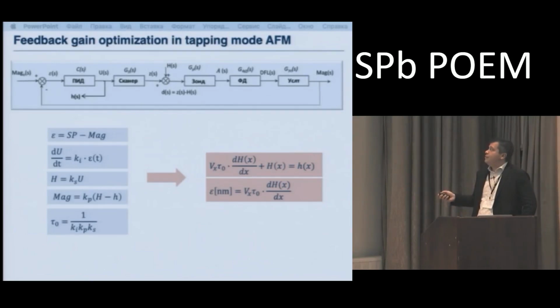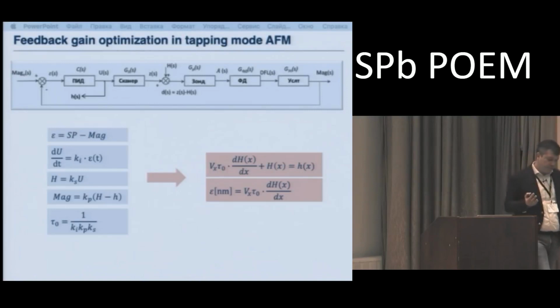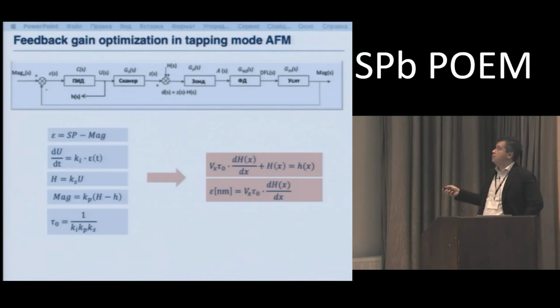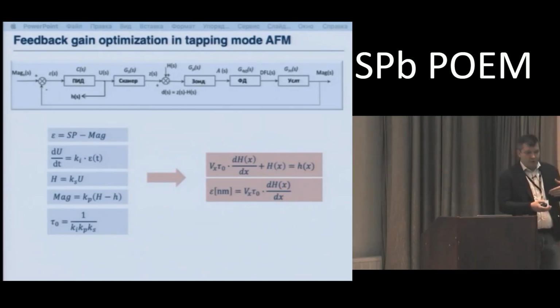to the scan velocity, some time constant, and derivative of the topography. This is a very simple relation, but it gives a quite simple idea. If we have a good scanner that allows us to scan not with the constant scan speed, and if we want to keep the error signal within some limits, we can adjust. If we have the rough topography, so this derivative is higher, we can decrease the speed. Or if we have the quite flat sample, quite flat topography, we can increase the speed of scanning.